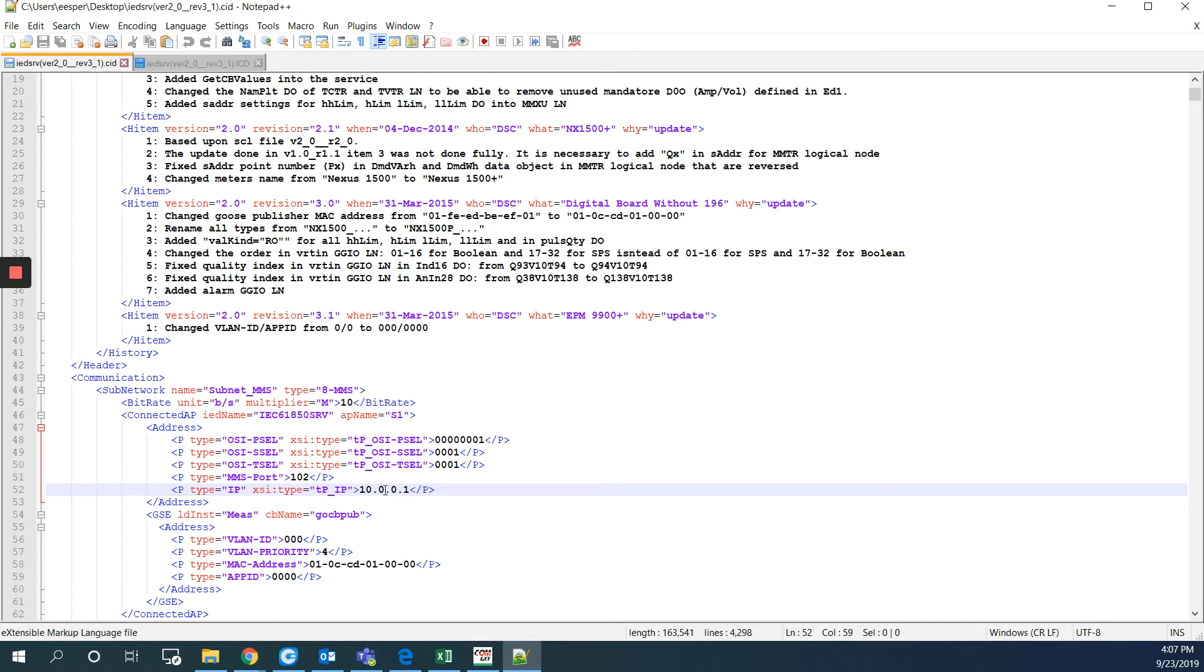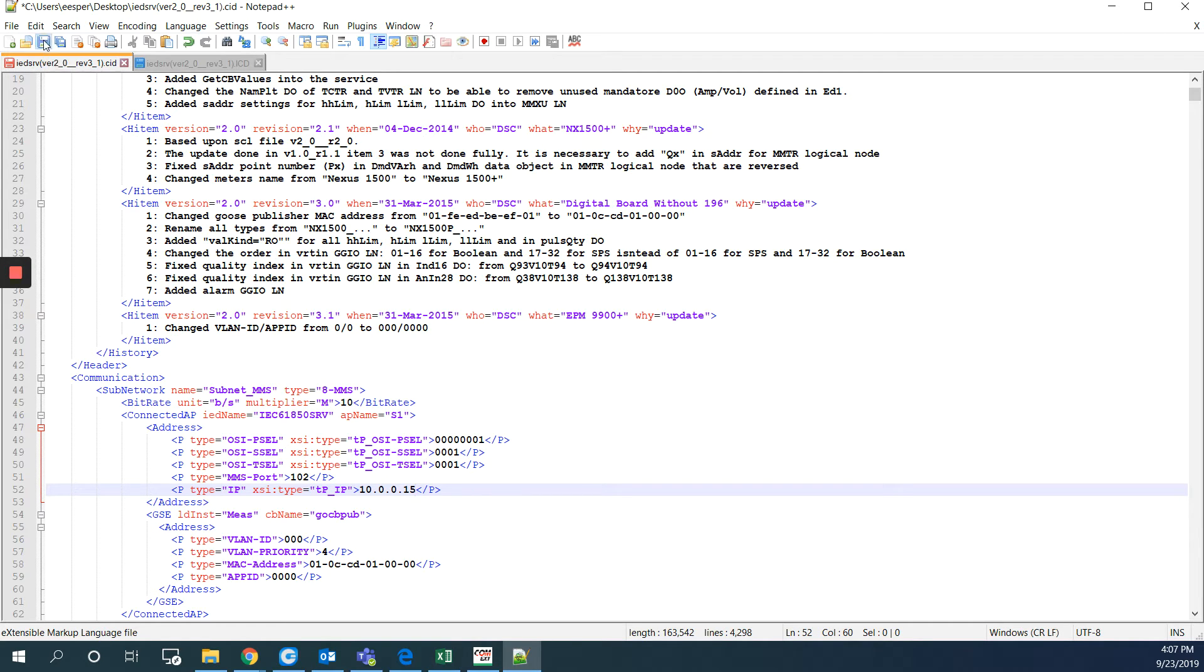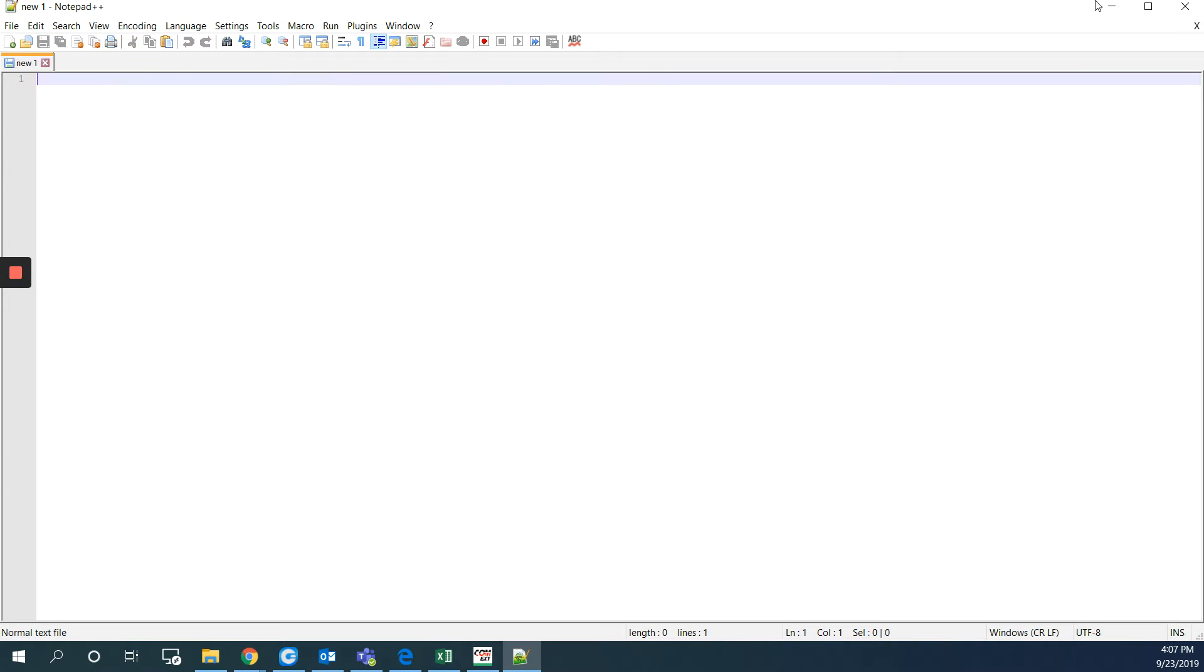The default IP address is 10.0.0.1. And this is the default IP address for the Nexus 1500 plus. But my meter's IP address is 10.0.0.15. So I will change this to the same 10.0.0.15. I will hit save and I can close this.